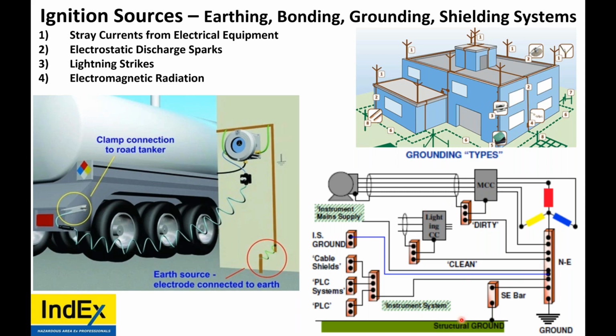Then we have our protective earthing and grounding systems, our instrumentation clean earth. We also have our functional earthing and intrinsically safe earthing. All of the instrument, clean earth, and intrinsically safe earthing has to be isolated from each other and from the regular earthing systems. Why? Because if you have circulating currents, you can have a potential source of ignition.